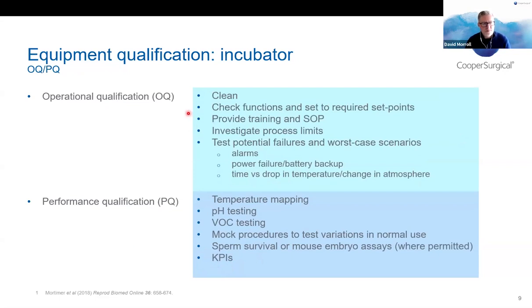In terms of operational qualification, that's around getting that newly installed piece of equipment to the point where it's usable, in our case in the clinical setting for our embryology procedures. So it means cleaning it, checking the functions, making sure it's appropriately set up to the required set points. And of course, those are user set.